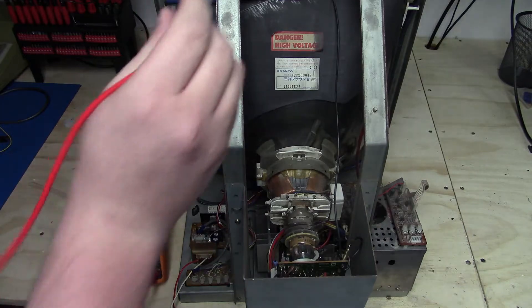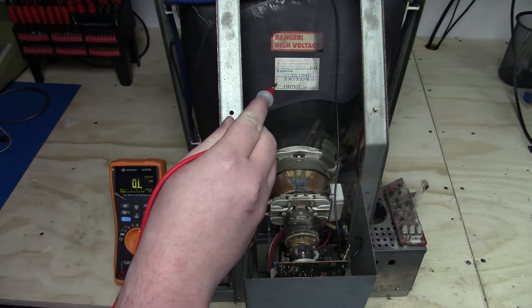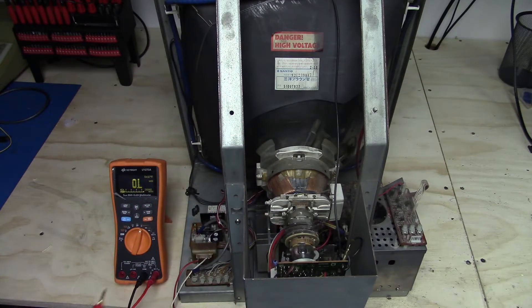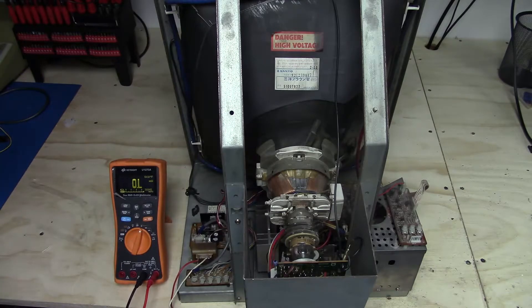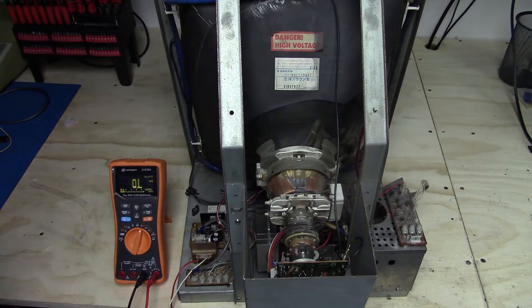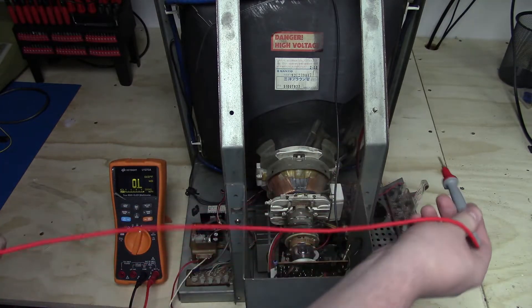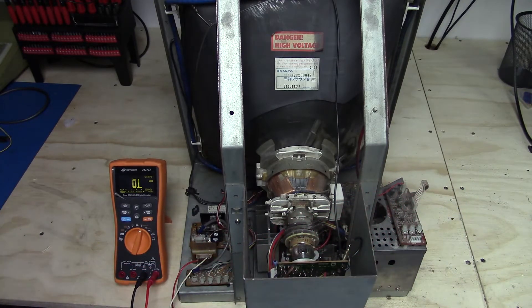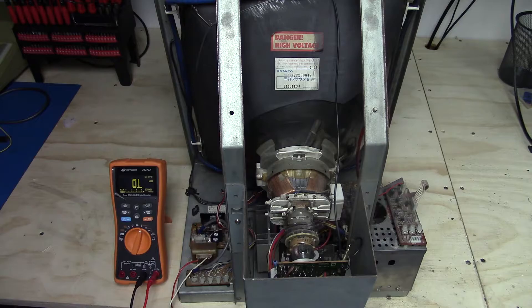Well, because this is a very, very high voltage capacitor. You can think of it like a 20,000 volt capacitor. And you need two sides of a capacitor to be connected for it to work. And in the case of the, I guess you could say it's the anode, right? It's the anode. That's this guy here. So where's the cathode? Well, the cathode is the tube itself.